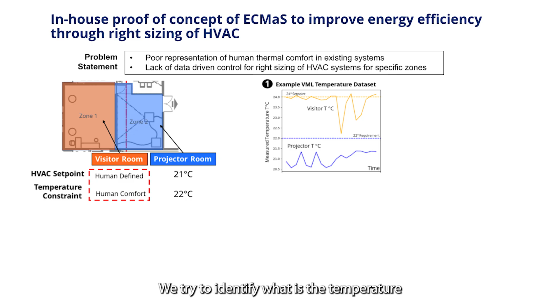It consists of environmental factors along with human factors, shown right here, and has a scale from +3 to -3. We then want to move our current temperature data to more optimized control, and this is what the magic of ECMAS does: it tries to provide an optimized temperature set point that dynamically adjusts to the requirements.